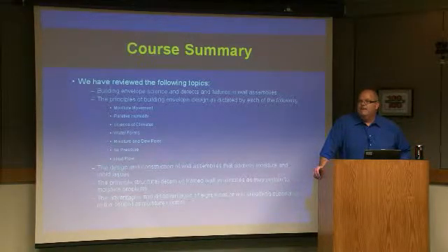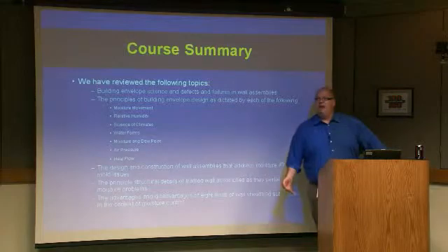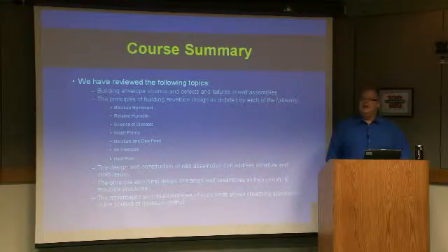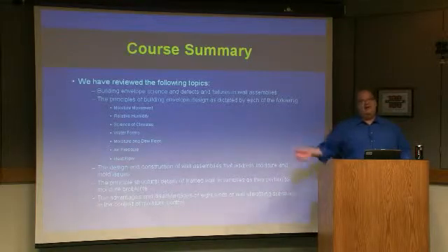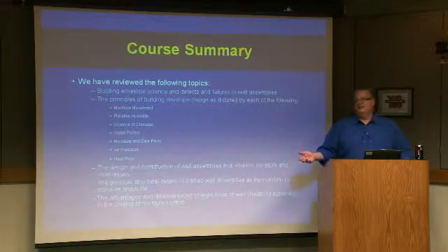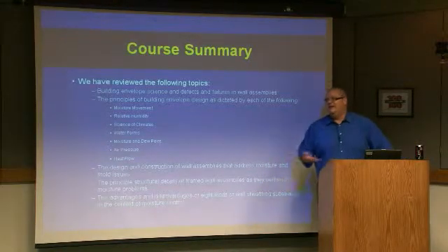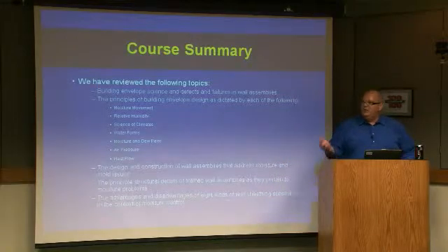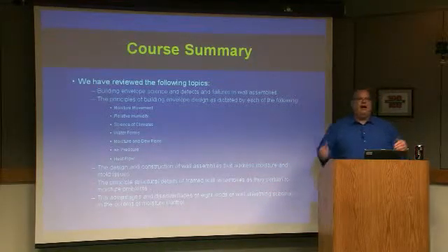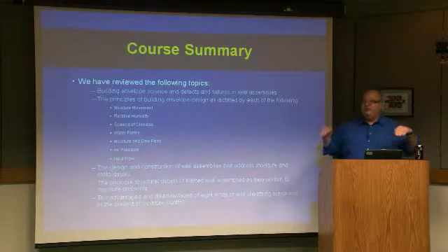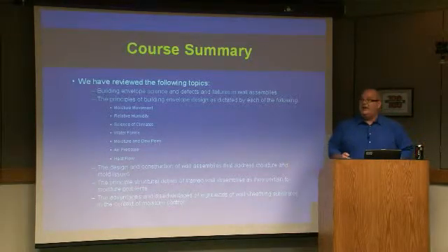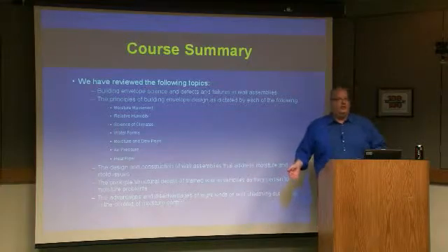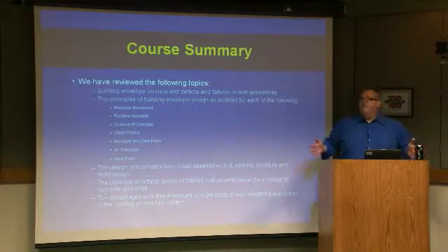Except you're saying in a basement against the block wall? No, below the slab. Not in the walls, below the slab. Okay. Yeah, basement walls are really tricky because the ground on the other side is 53 degrees. It's not that unfriendly to the inside. The problem becomes with moisture, especially when you have a walkout basement. If you've got a basement that's partially below grade, typically the moisture drive there is going to be from outside in, because the ground outside is going to have a higher moisture content than the room. So you get a moisture drive in below grade.